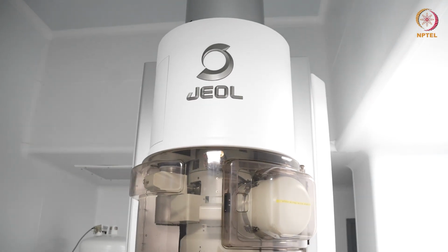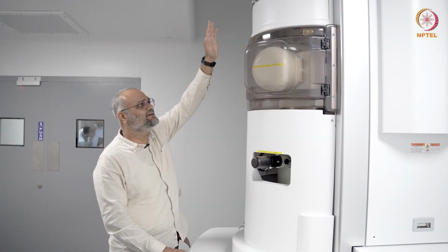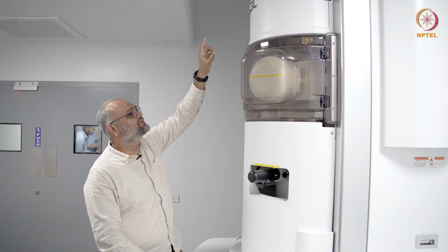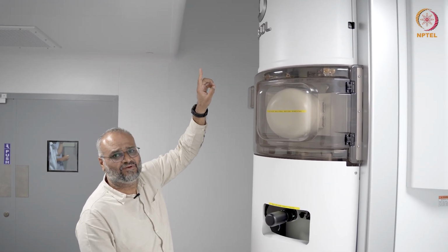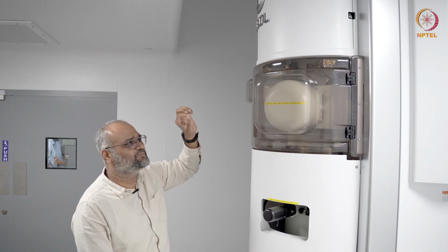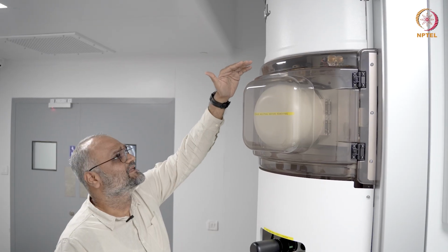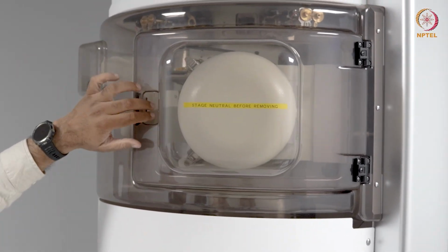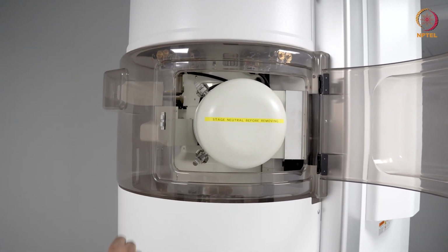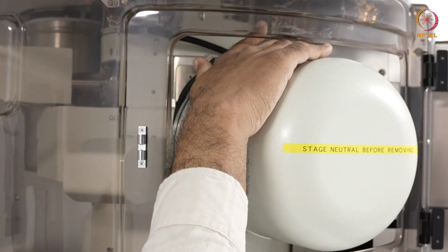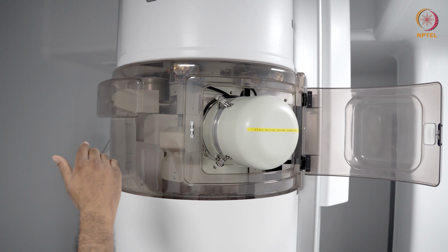So on the top here, you have the field emission gun. This is exactly the same kind of field emitter that you saw on the F200 microscope as well. So by electron tunneling, at low temperatures, we have the emission of electrons and we form a very coherent probe. And as we go down, we have a series of condenser lenses here. This instrument has all automated apertures. If you can come closer, I'll show you where the apertures are.